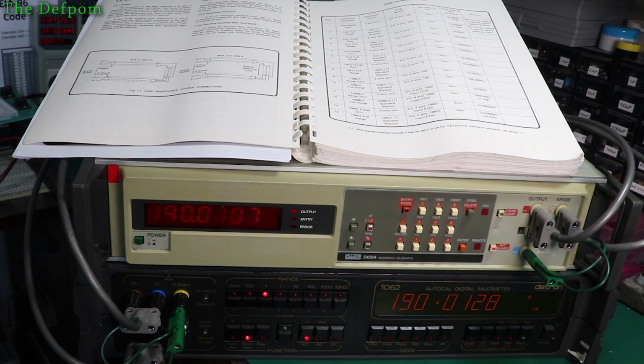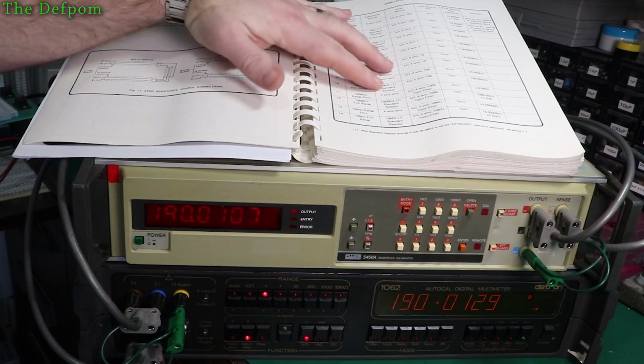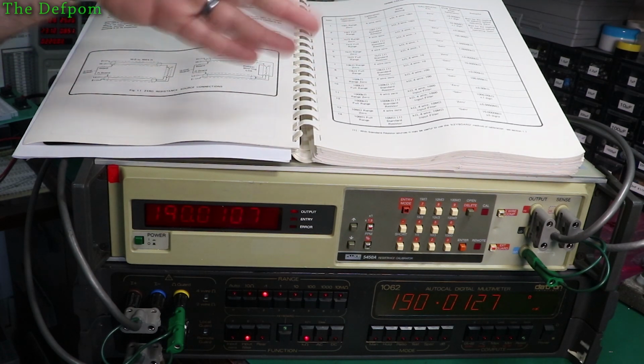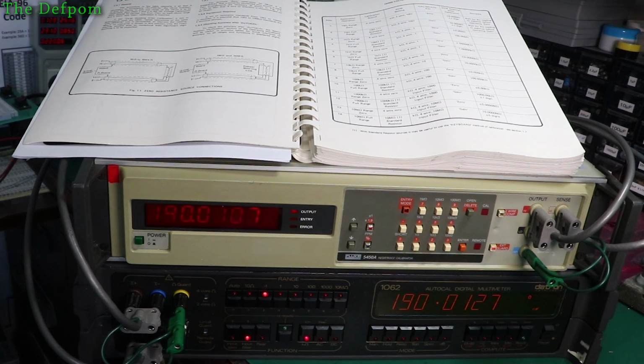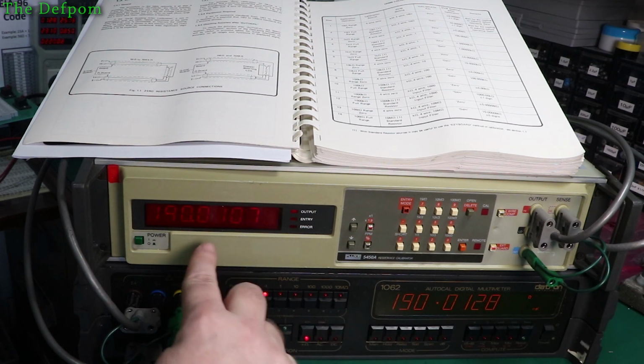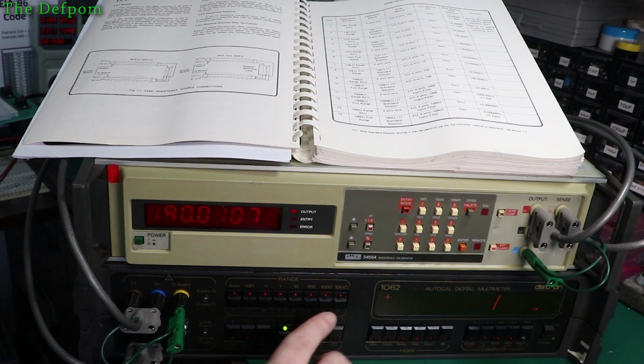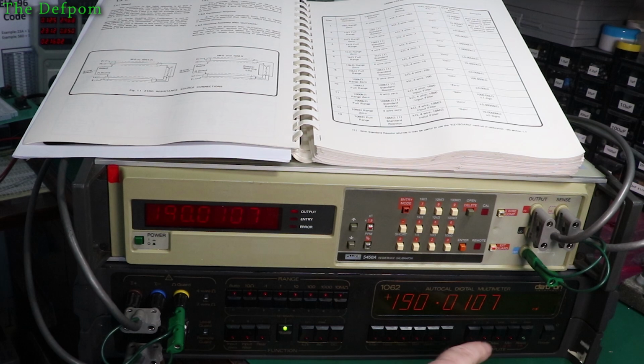So what I'm going to try, just for fun, on this particular range, is miscalibrating it. The manual says to use the middle of the range, right? I'm going to use the top of the range. I don't know if it will work, probably won't accept it because it has to be within a certain tolerance, otherwise it just won't go. So we could try it and see. If I'm outputting this value and I try to calibrate to this, shall we? So we do it. 190.0107. Alright, so that's what we've got on here. Will it accept it? It did accept it.